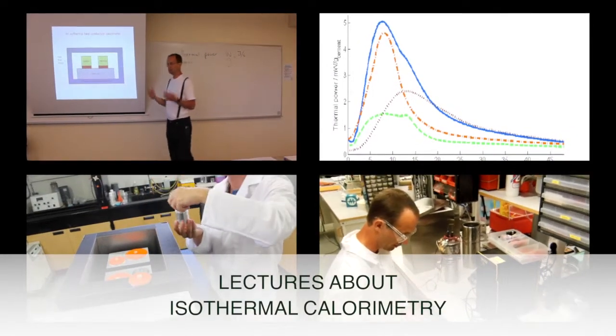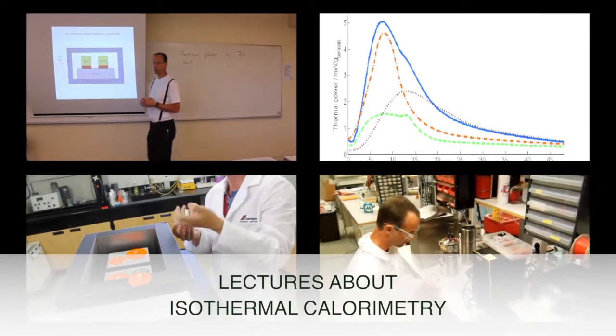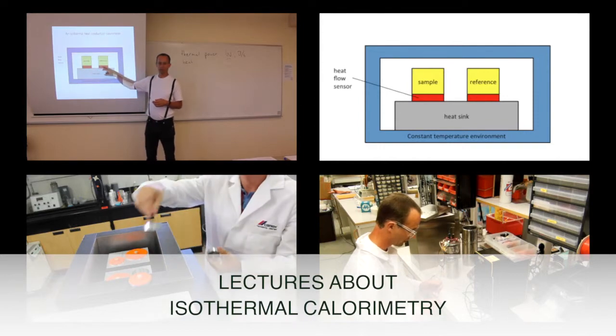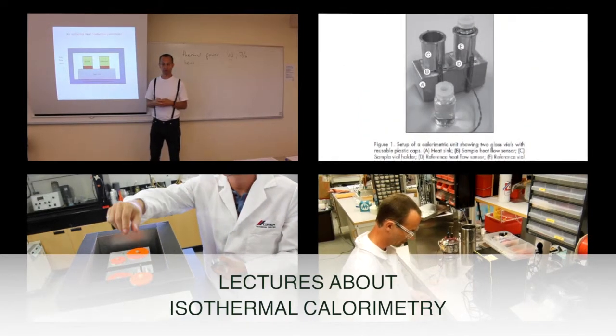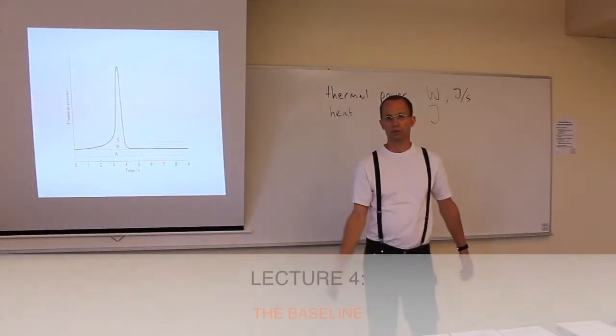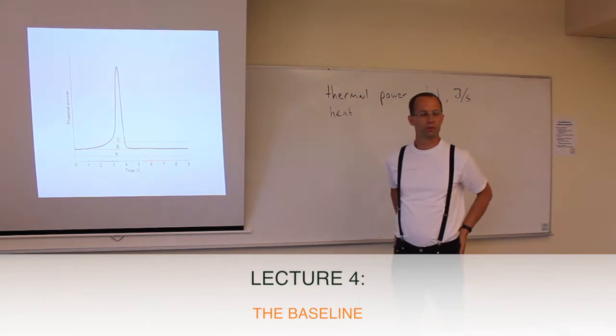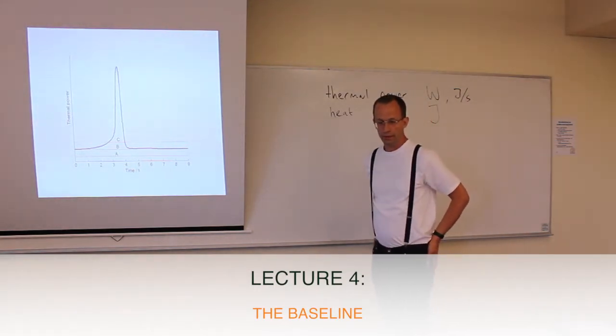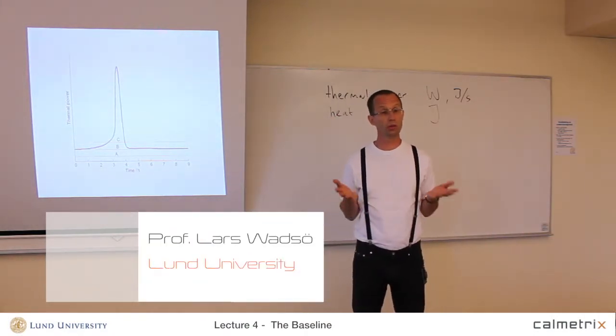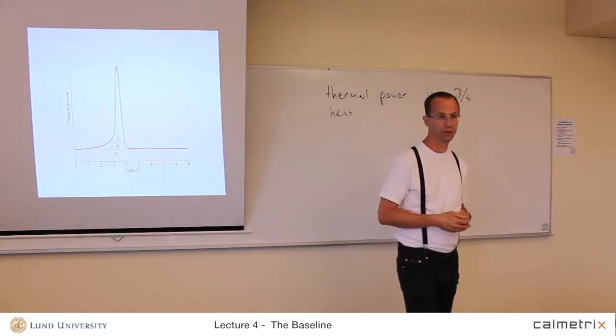In this lecture I will talk about the baseline, also called the offset. This is the signal from the calorimeter when there is no heat produced — no thermal power, zero thermal power. That signal is what we call the baseline.